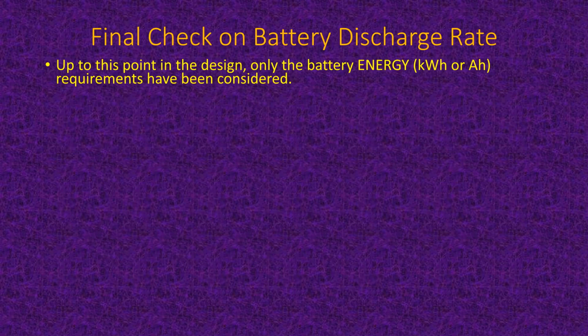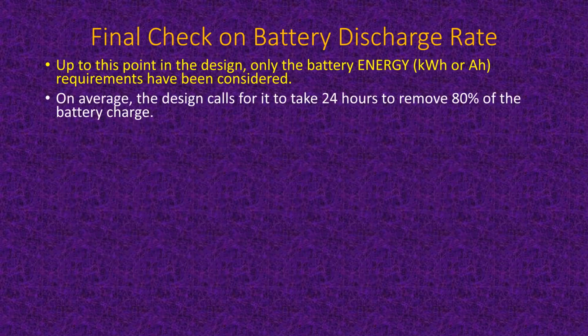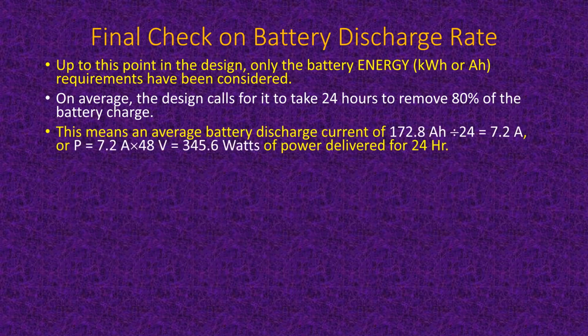So let's check the battery discharge rate. And again, we were talking about 24 hours to remove 80% of the battery charge. So what's the power you can use? Well, that means that 172.8 amp hours is 80% of the charge.